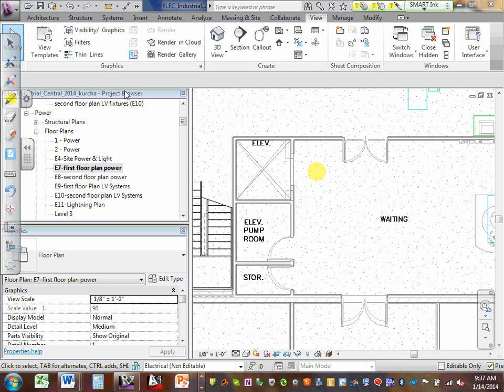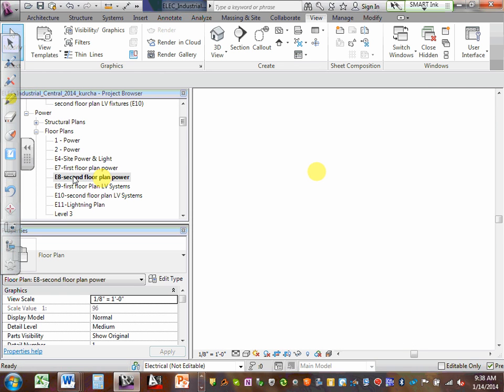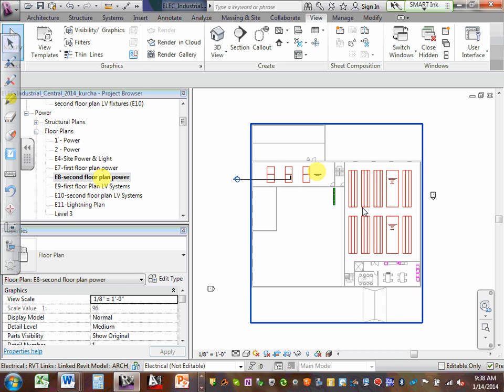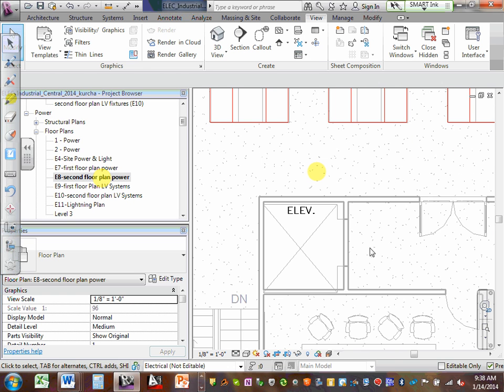In other words, we can't have that elevator stop on that floor, because you don't want somebody in the elevator to have the doors open and walk into a fire. Okay? It's pretty simple stuff. So every elevator lobby has to have a smoke detector, and that would be within 21 feet of the elevator door on the ceiling. Second one. So it would be one on the 1st floor and one on the 2nd floor. Okay.